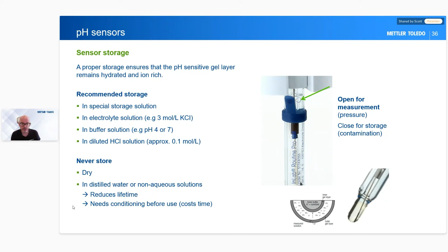The second one is we never use distilled water. If we use distilled water here, what will happen is the hydronium ions inside here will leach out, and then it's very difficult to get them back in again and keep it ion rich to allow the flow of ions in and out. When this becomes depleted, then it won't work. So what we need to do is make sure that we're using one of these recommended storage solutions. At worst, table salt in some tap water would be better than nothing. Then I would highly recommend you get hold of one of these solutions if you don't have one in the lab already. But never ever store it dry, never ever in distilled water.